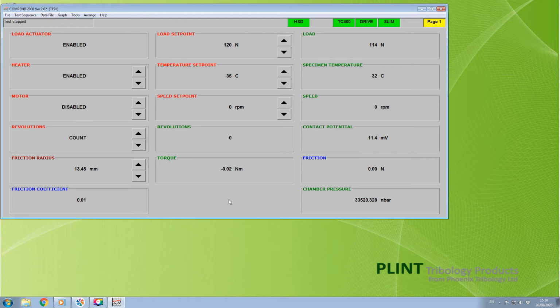Note that large step changes in temperature set point are likely to cause the bath temperature to overshoot the set point. So under manual control, use small set point increments when adjusting the temperature. This issue is avoided with automatically controlled tests, where it is recommended that ramped set point changes are used.